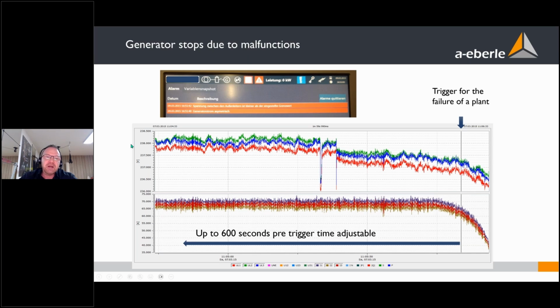Then I need 600 seconds before something happened, and now I'm analyzing what the problem was. In this case, there was a really small voltage change and the generator reacts to it. But it's only a voltage dip of 2%, and no analyzer normally would recognize this with a threshold. Often you have plus or minus 10%. So it is much easier to trigger on a binary input, or I take the current. If something stops, I'm interested in a long pre-time to analyze what happened.